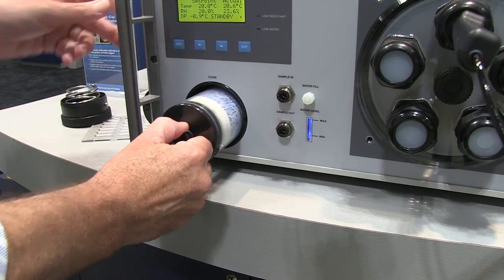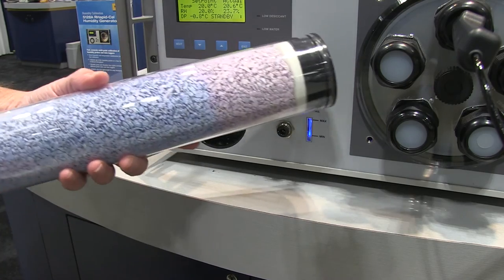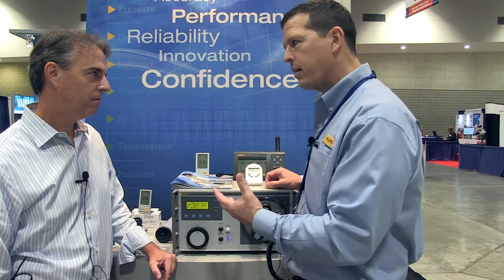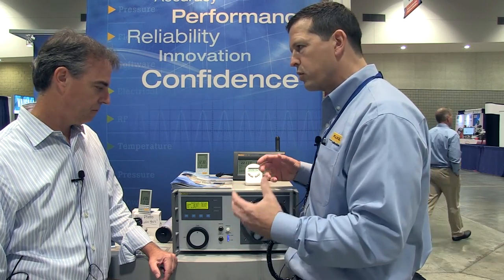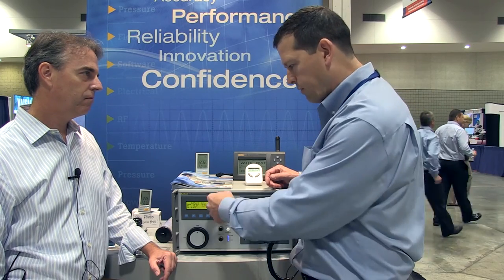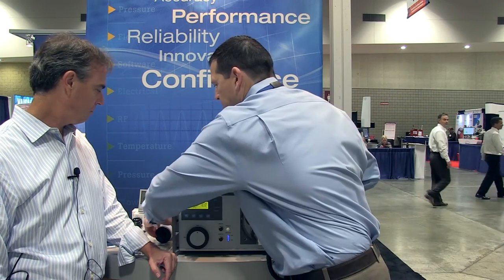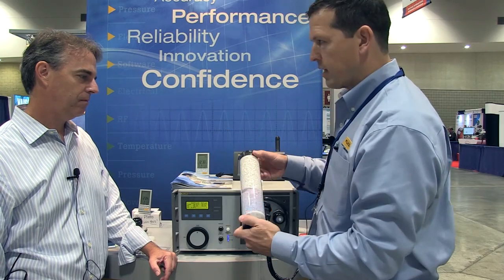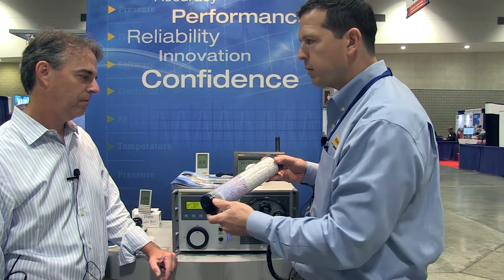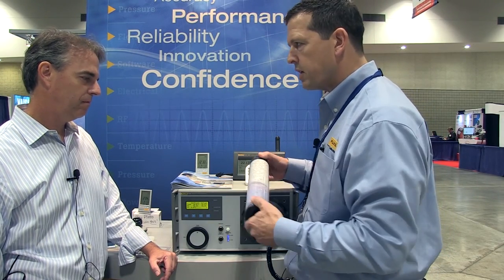You'll get an indication on the unit if it needs to be changed, based on its operation. It can tell if you have low or consumed desiccant where you need to change it, and it will give you a warning on the screen. The desiccant chamber looks like this, and the indicator outside, by color, will tell you whether it has been consumed and needs to be changed out.